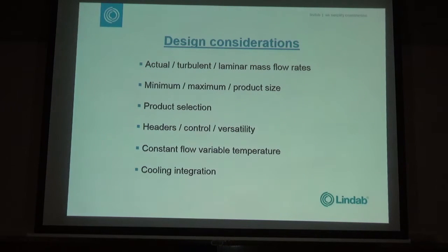Because as the temperature or your requirement goes down on your panel, you still maintain a turbulent flow rate on it. But it's one of the biggest things. I've been to a lot of jobs where people say these panels aren't getting hot enough, and the reason is because it's laminar and you're not getting 100% heat transfer. Just to give you an idea, that's about 20% of your capacity, so you're only doing 80% of the capacity of your plant.